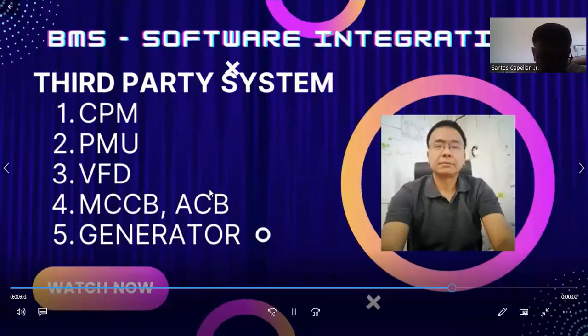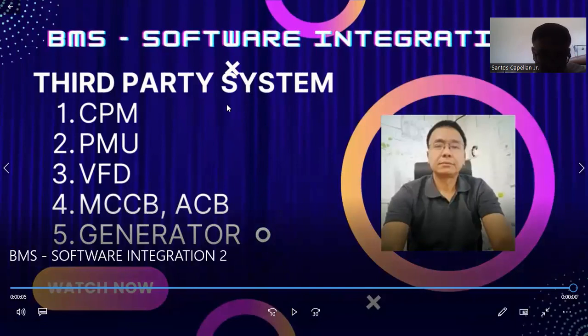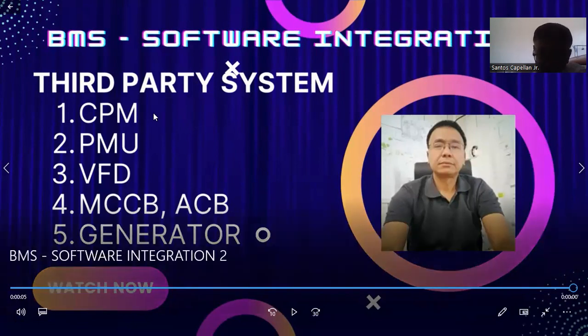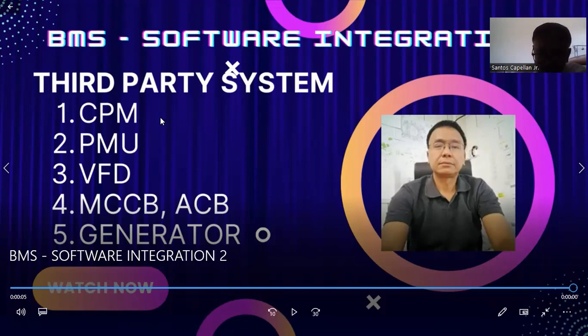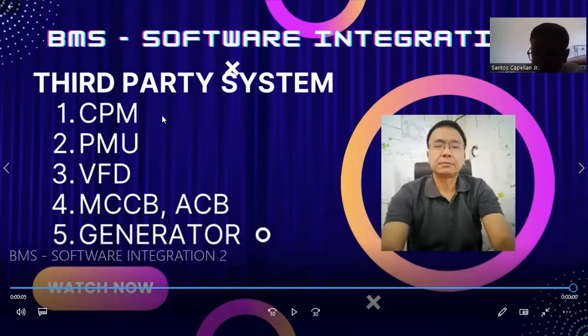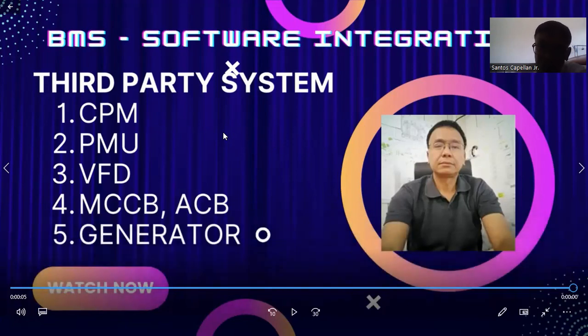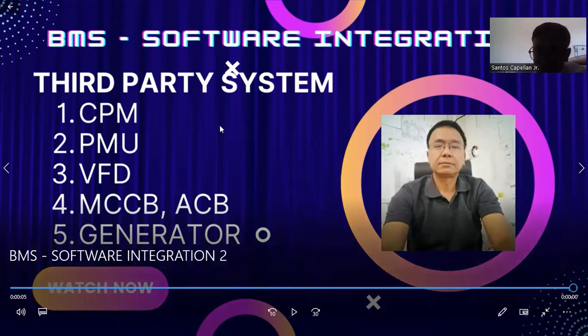So this will be my BMS Software Integration for third-party systems. A third-party system may be using the same communication protocol as your BMS system — maybe BACnet over IP or BACnet MSTP. So software integration is when you use a single communication cable pulled going to the third-party system, connected to our network controller or automation server.